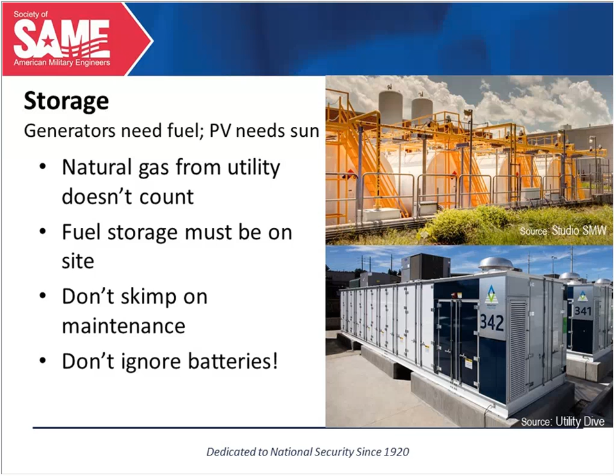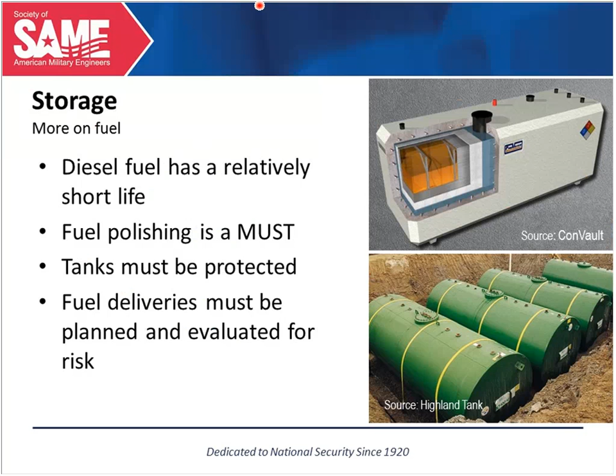Back to diesel fuel, since that's by far the most prevalent means of storage. It's really important that we all realize diesel fuel has a very short life. You can't just fill a belly tank in a generator and let it sit for 3 years and think that generator is going to run right when you need it. There's an amazing array of microbes that grow in diesel fuel. Diesel fuel absorbs water and a whole lot of other contaminants. So filtering the fuel and additives in the fuel are incredibly important. Collectively, that's called fuel polishing, and it can be time consuming, especially at a larger facility where you may have 100 generators. Between exercising the generators and making the rounds to clean and filter the fuel, that can eat up a lot of time and expense.